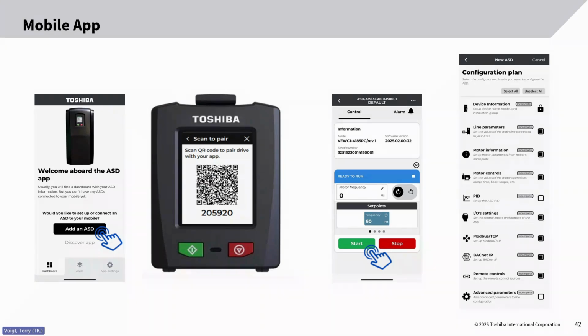Additionally, in the screen, we also are able to program the drive and monitor the drive using an app. So the app is available for both Android and iPhone. And it connects through Bluetooth. So you can pair the device, so it can also work with like a tablet. You pair the device to the drive itself. You can pre-program it and then send the program into the drive. You can very easily duplicate programming that way, or you can just for safekeeping do a similar type of configuration.